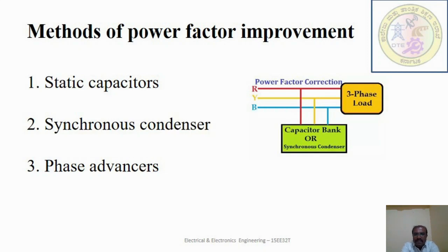So power factor correction may be required where a system has a power factor less than 90%, we can say 0.9. A poor power factor can contribute to equipment instability and failure, as well as significantly higher energy cost, since more current is required to perform the same amount of work. By optimizing and improving the power factor, the power quality is also improved, reducing the load on the electrical distribution system.